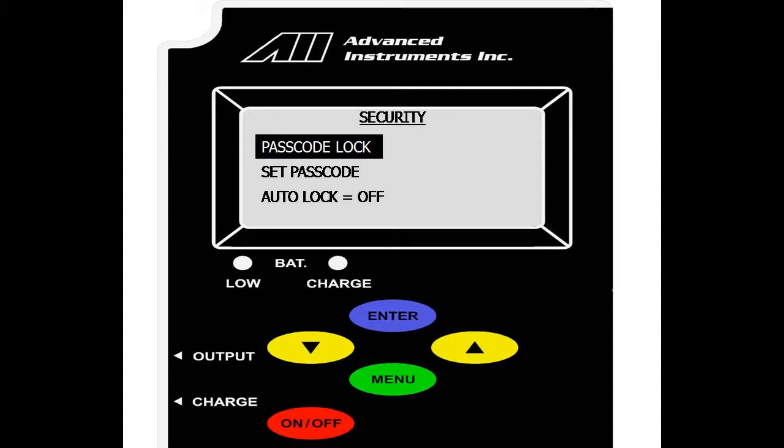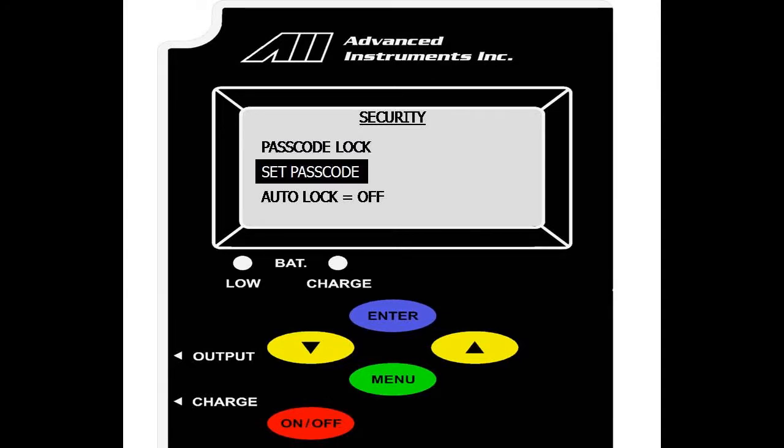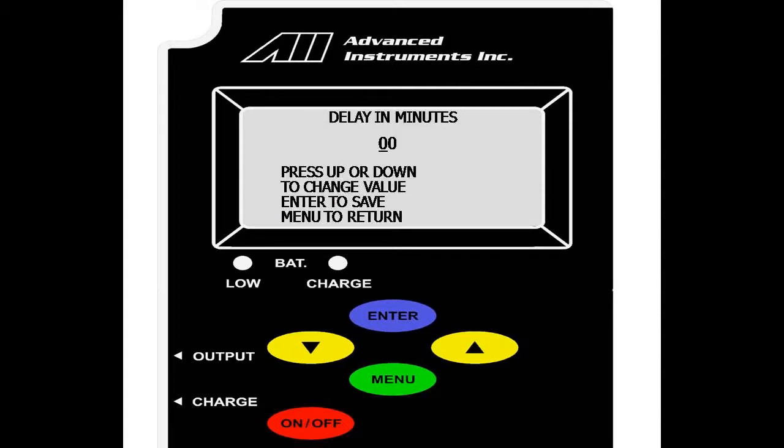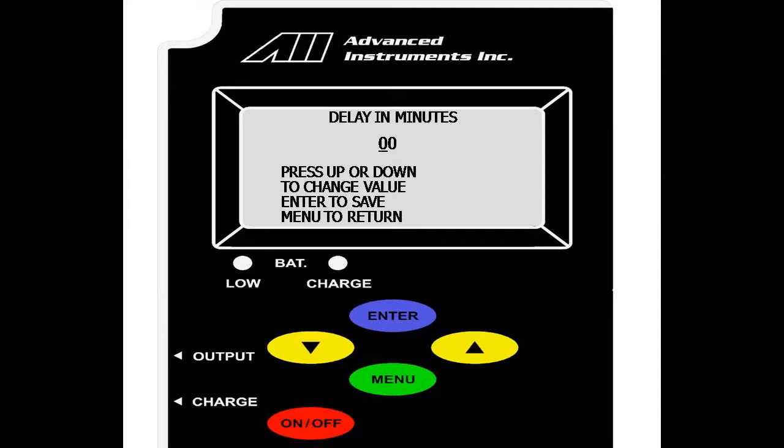This will lock the analyzer down and anybody that would like to enter the main menu is required to enter the four digit passcode lock. You can also set an auto lock option, select enter and set a delay in minutes. This allows the analyzer to auto lock itself with the passcode after a certain amount of minutes from being idle.